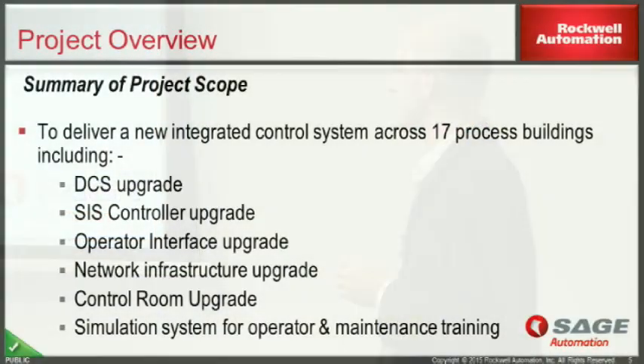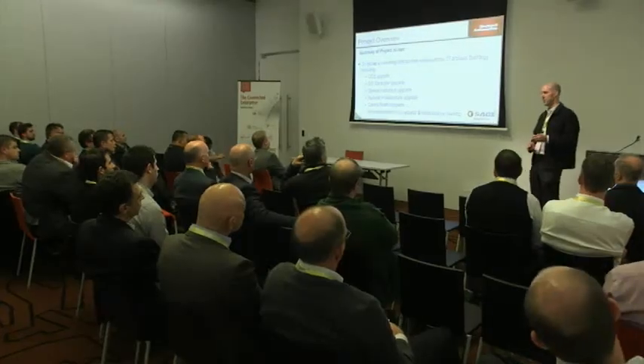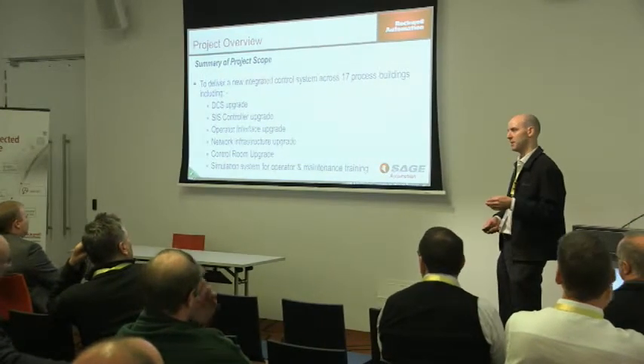hazardous area requirements. So the summary of the project, we were to deliver a new integrated control system across 17 process buildings, including the DCS upgrade, which is the Toshiba to the PlantPAx, controller upgrade, which is from old Modicon 984 PLCs to the Rockwell AADvance, operator interface upgrade, network infrastructure upgrade, including cabling, control room upgrade, complete refurbishment of the control room, and we delivered a simulation system for operator and maintenance training, but we also utilised that for our internal FAT purposes.